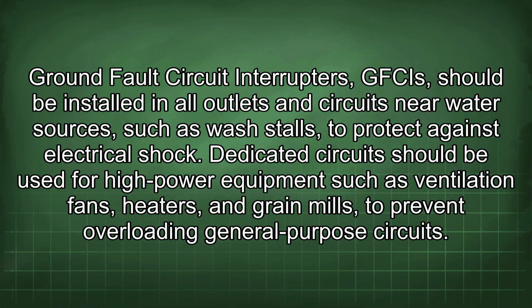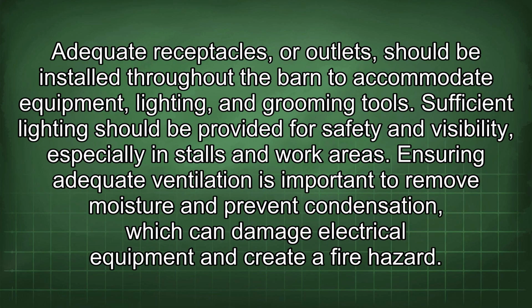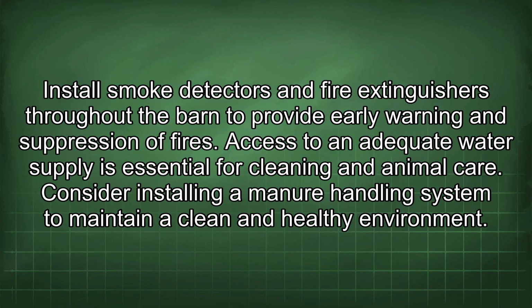Dedicated circuits should be used for high-power equipment such as ventilation fans, heaters, and grain mills to prevent overloading general-purpose circuits. Adequate receptacles or outlets should be installed throughout the barn to accommodate equipment, lighting, and grooming tools. Sufficient lighting should be provided for safety and visibility, especially in stalls and work areas. Ensuring adequate ventilation is important to remove moisture and prevent condensation, which can damage electrical equipment and create a fire hazard. Install smoke detectors and fire extinguishers throughout the barn to provide early warning and suppression of fires.